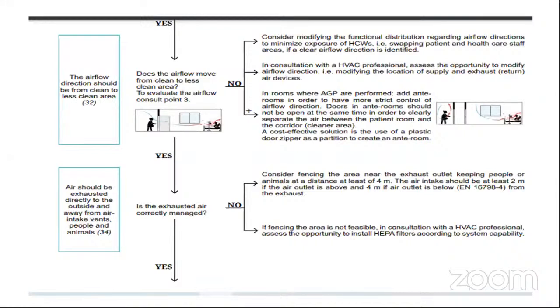The doors in the ante-room should not be open at the same time. And like I have already said, if we can use a plastic zipper as a partition, that would be a more cost-effective solution. Is the exhausted air managed correctly? According to WHO, the same 4 meter distance from people and 2 meters from the air outlet above, and 4 meters if the air outlet is below, from the exhaust.